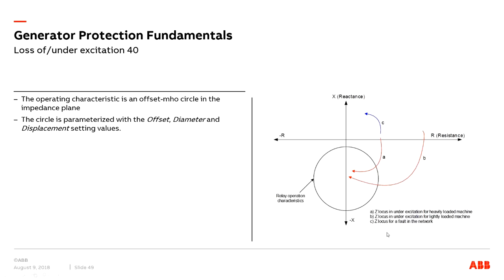So you can see here A is an impedance locus in an underexcitation condition for a heavily loaded machine, and this is the impedance locus in an underexcitation condition for a lightly loaded machine, whereas C is an impedance locus for a fault in the network. If the impedance locus enters this relay operation characteristic, which is an offset Mho, then we call it a fault situation, and the relay is called to trip.